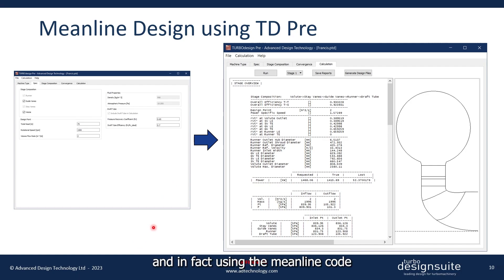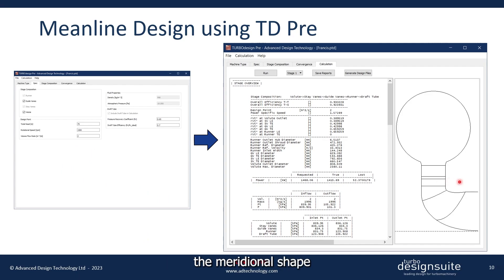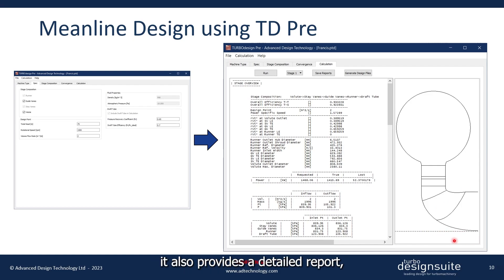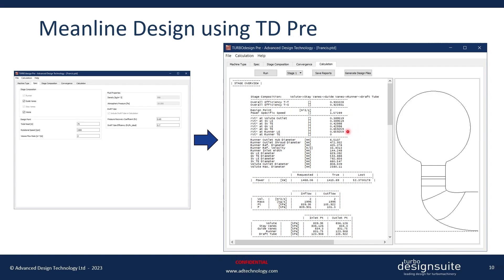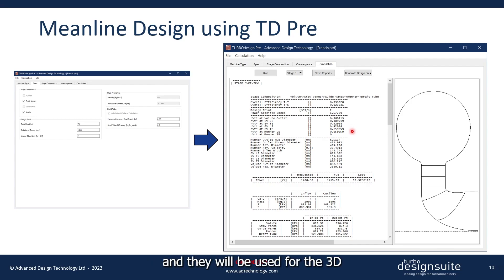Using our mean line code TurboDesign Pre, it's very easy to enter the given specs and it quickly generates the meridional shape of the Francis Turbine stage in less than a second. As you can see, it also provides a detailed report including the estimated stage performance, some important dimensions, and the required RVT* for the stay vanes, guide vanes, and the runner. These RVT* values for the different components are equivalent to their work coefficients and will be used for the 3D inverse design of the vanes and the runner in the next session.